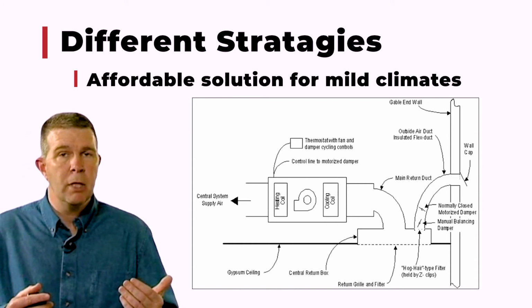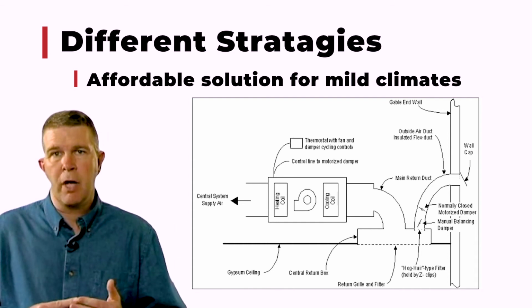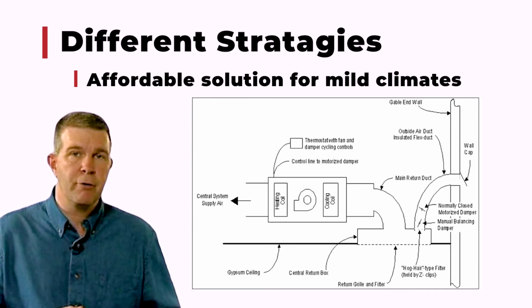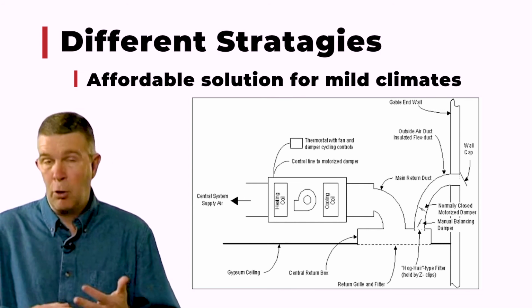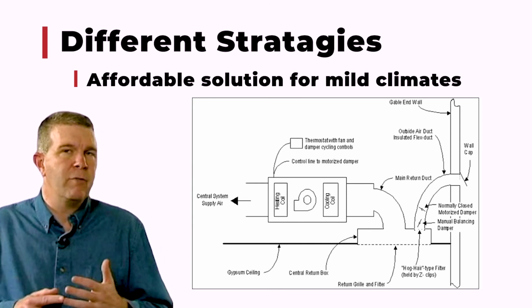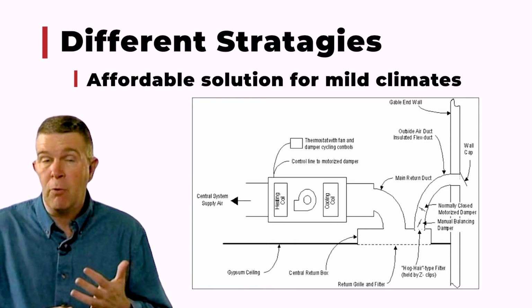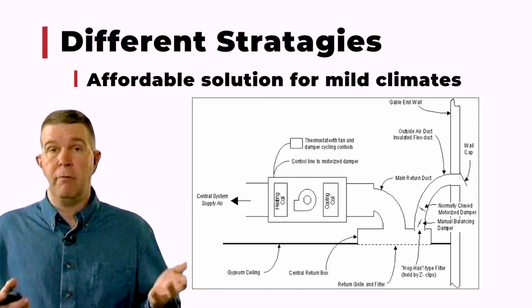Relatively mild climate, but what we do is we simply use a fan cycler switch. For about $112, we've got a fan cycler detector that knows how long the air handler has been on. We bring in small amounts of fresh air through a ducted line, and that ducted line has a balancing valve in it, and it also has a motor-operated damper. Well, it's pretty simple. For $200 or $300, we have the installed cost of a supply strategy of fresh air that comes into the air handling system, which is already running. And with the right type of air handling system, our operational costs are very minimal.